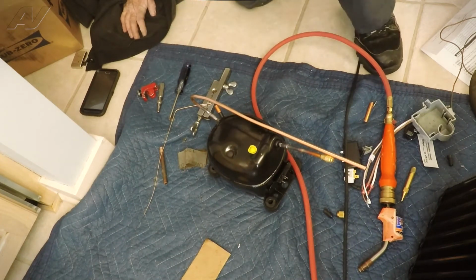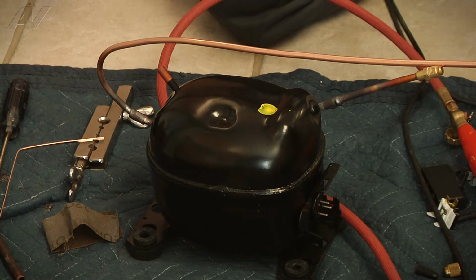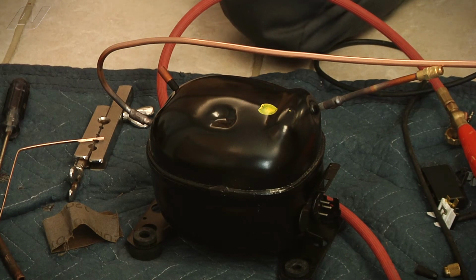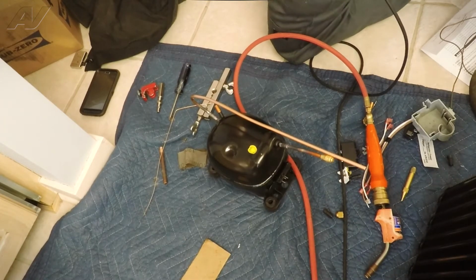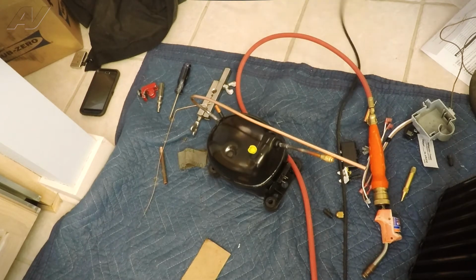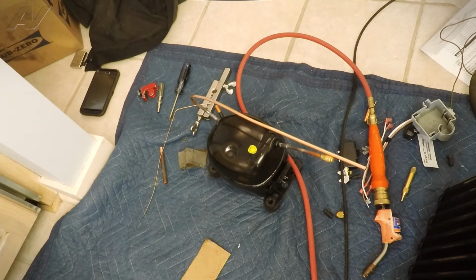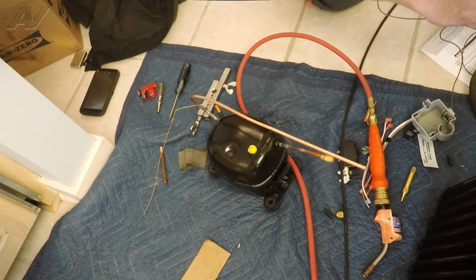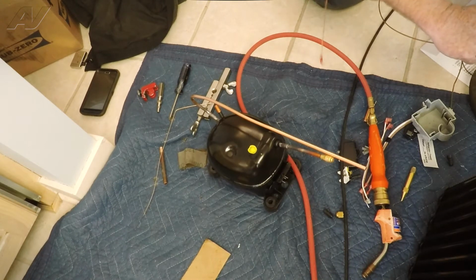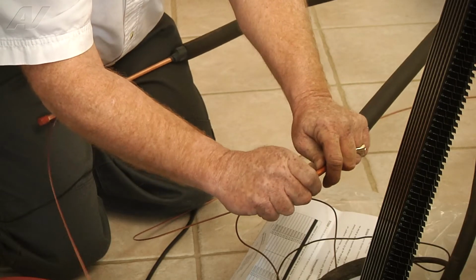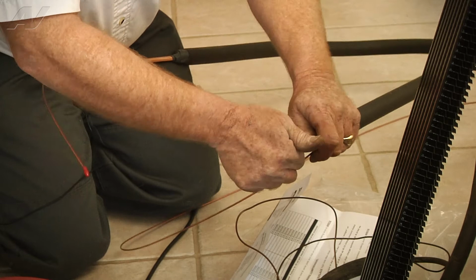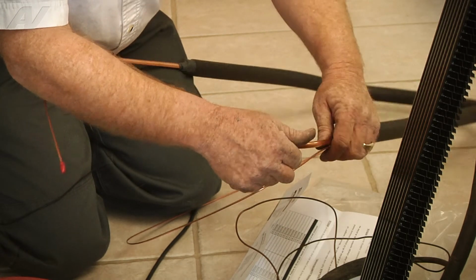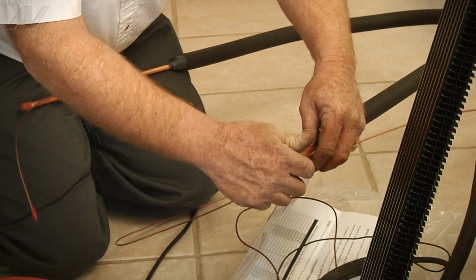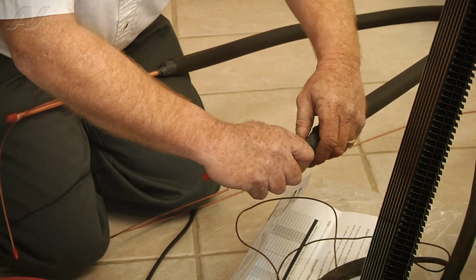You'll actually be able to see the pipe start to change color, and then your braze will flow like it's supposed to. Now, while that's cooling down, let's go to our heat exchanger. The part of the heat exchanger with the longest section of capillary tube is the part that's going to connect to the compressor. So we're going to utilize the old heat exchanger, and we are going to simply mold the tubing so that it will fit onto the compressor, much the same as the old one did.